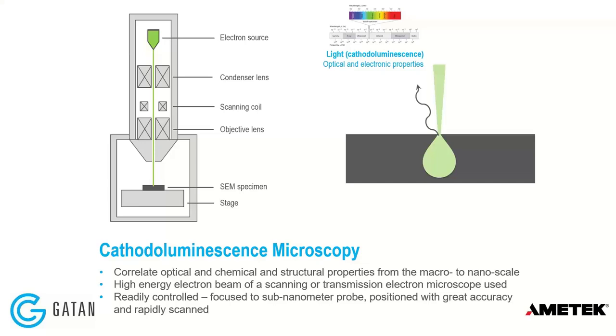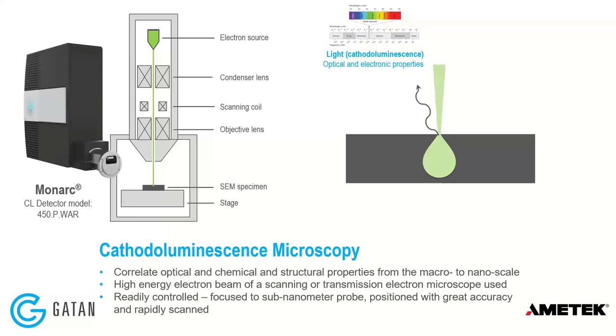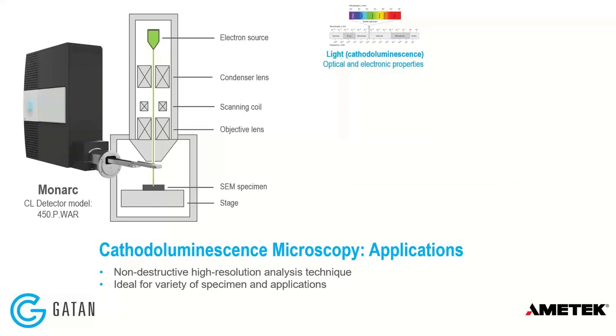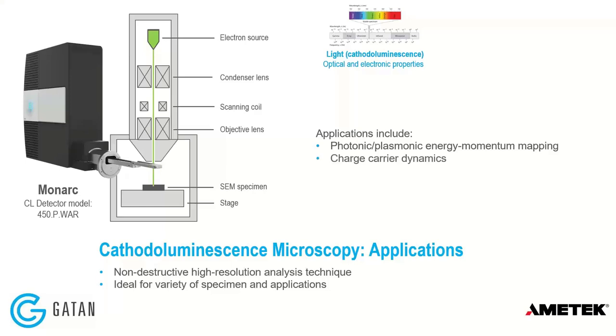We're basically piggybacking off of the electron microscope's ability to focus to a very small spatial resolution. We bolt on a cathodoluminescence detector and insert an arm into the beam's path, where the beam passes through an aperture in the mirror, and the light is coupled back into the system for analysis. CL microscopy is non-destructive and has very high spatial resolution. It's ideal for photonic and plasmonic energy momentum mapping, charge carrier dynamics, stress and strain mapping, crystal defect mapping, and device characterization and failure analysis.